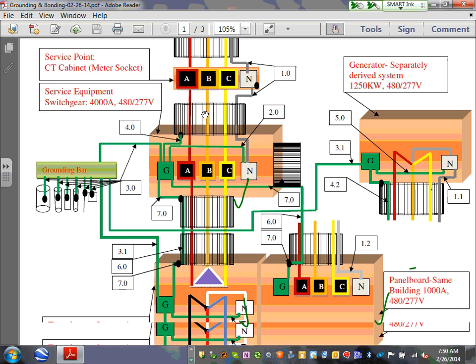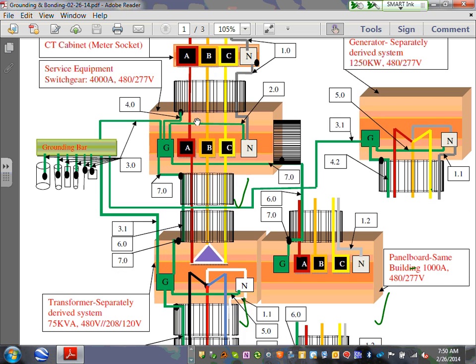So bringing the cables to the switchgear, 4000 amp, what do you do? You divide it by 10, you get your 400 amp, and go size your conductors. Now I want to bring to your attention, guys, since this is grounding and bonding, the numbers. Can I get you guys to look at the numbers? Do you see 1.0 and 2.0 and 4.0? The reason I put these numbers is because on pages 2 and 3, they're identified.